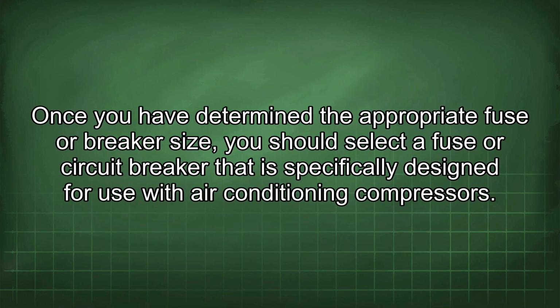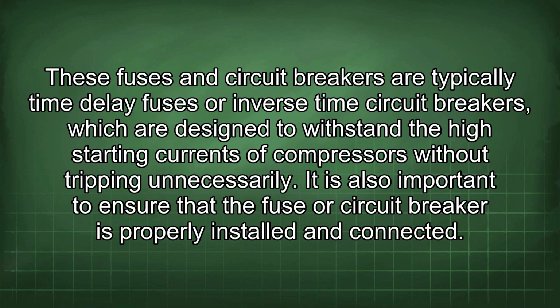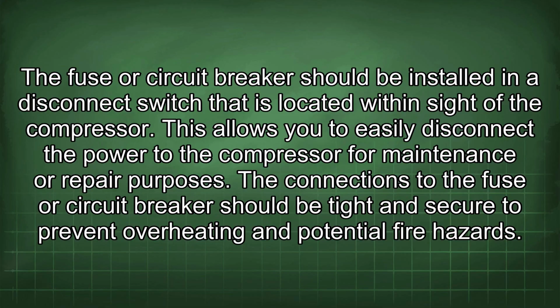Once you have determined the appropriate fuse or breaker size, you should select a fuse or circuit breaker that is specifically designed for use with air conditioning compressors. These fuses and circuit breakers are typically time delay fuses or inverse time circuit breakers, which are designed to withstand the high starting currents of compressors without tripping unnecessarily. It is also important to ensure that the fuse or circuit breaker is properly installed and connected. The fuse or circuit breaker should be installed in a disconnect switch that is located within sight of the compressor.